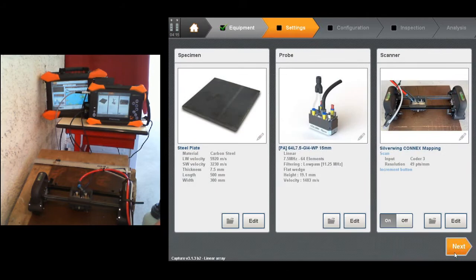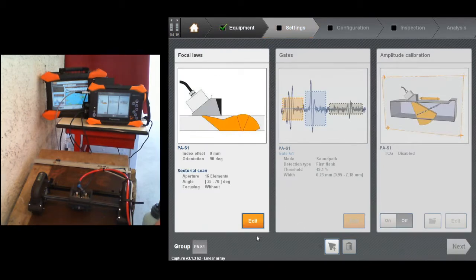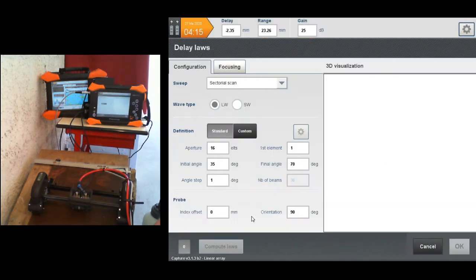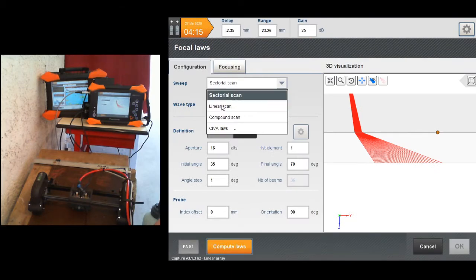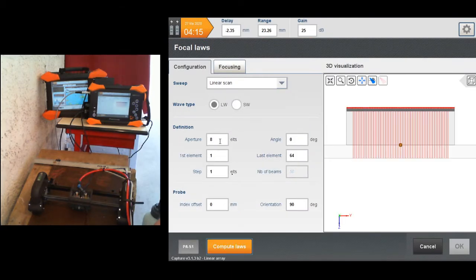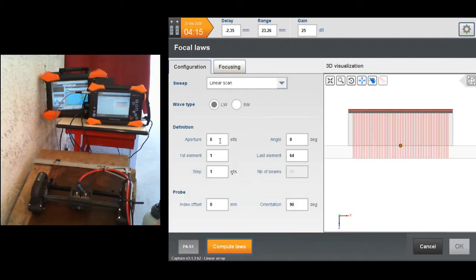Then I can follow the orange button and click on next. And the next step is focal law settings. I can edit, select linear scan, L waves. With this probe typical setup, we use 6 elements. So it gives me an equivalent active aperture of 6 by 7 millimeters, which is quite good for this kind of setup. And then I start from element 1 to 64. This means I have here 59 different beams. The coverage is 59 millimeter.